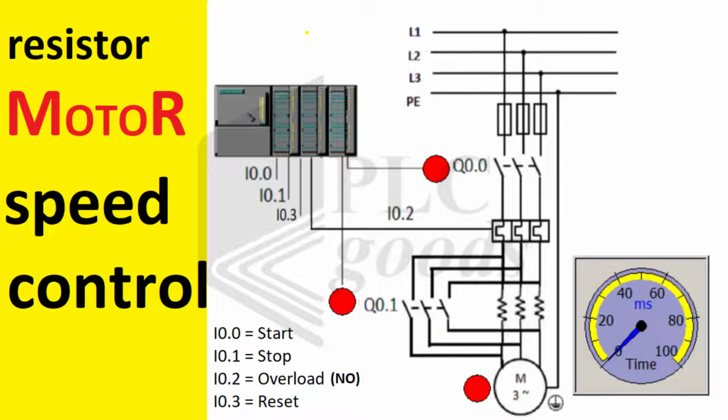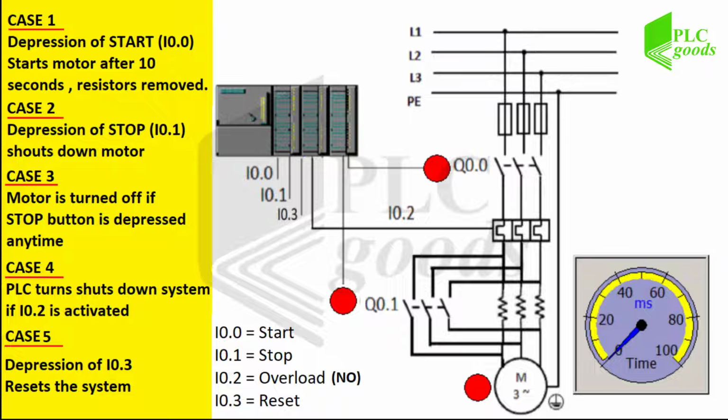Project number three is starting a squirrel cage three-phase motor with initialization resistors. We wish to develop a PLC control program based on the following conditions. Case 1, when the start or I0.0 push button is depressed, the three-phase motor starts by the presence of initialization resistors in series with the power supply to the motor.